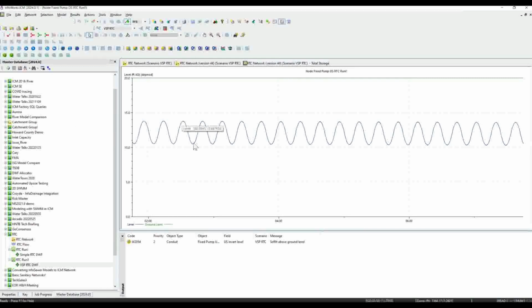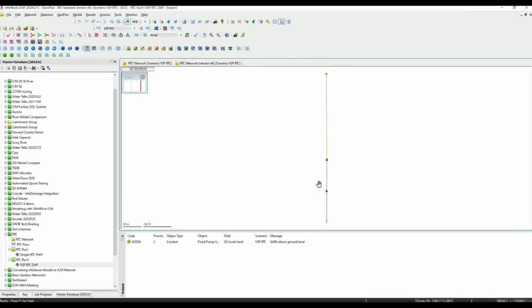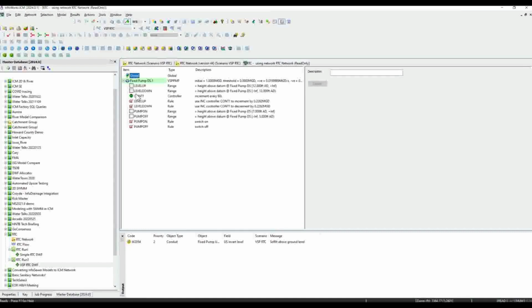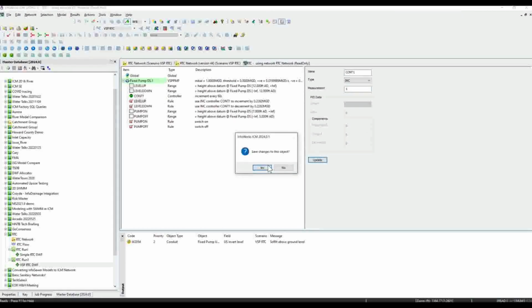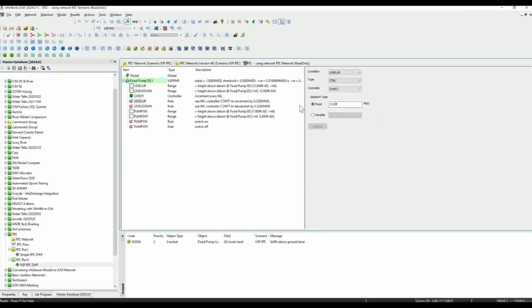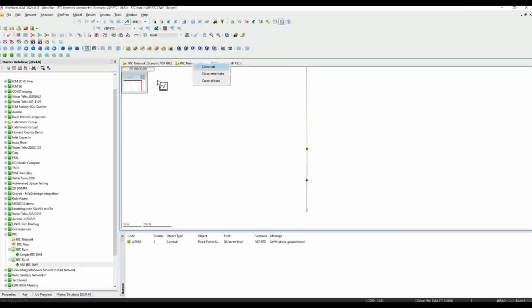You can see that that response is kind of sluggish in here. So we are kind of bouncing around a good bit. Somewhat similar to that time step, we have an issue with the RTC that's really causing that. If you remember in the controller, that was every 60 seconds. If we decrease it to something a little more frequent, we could also modify these level up, level down, incremental changes here to something a little higher to make that modification go a little bit quicker.